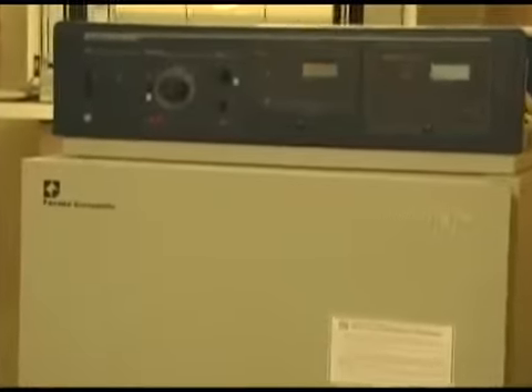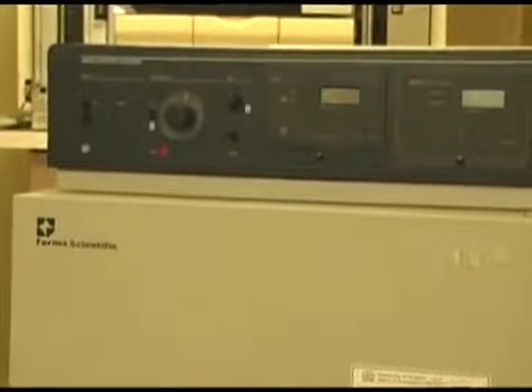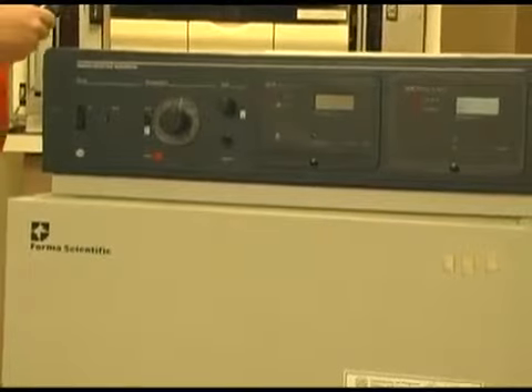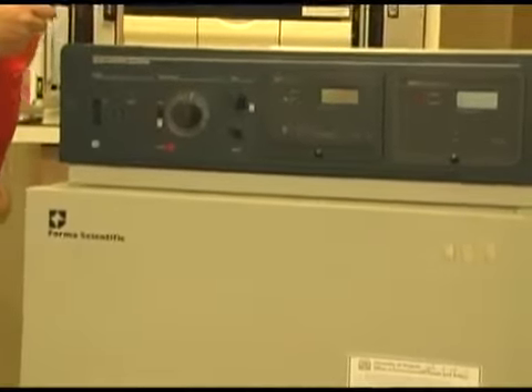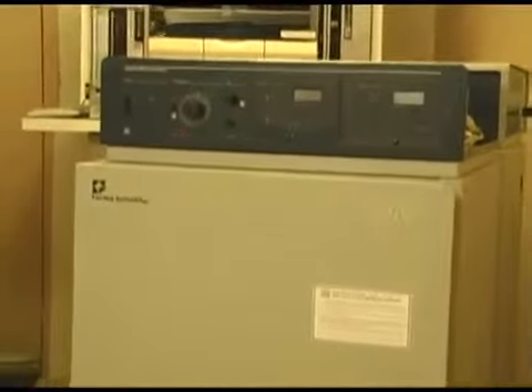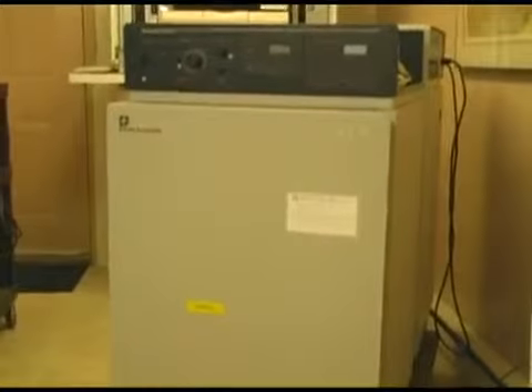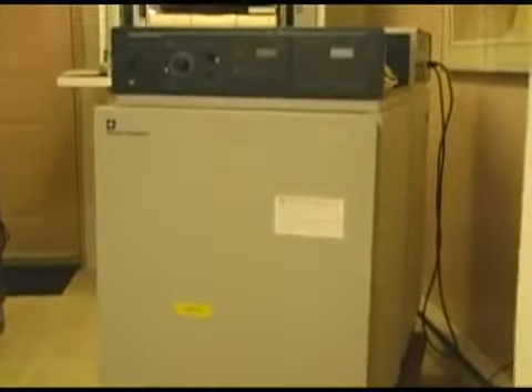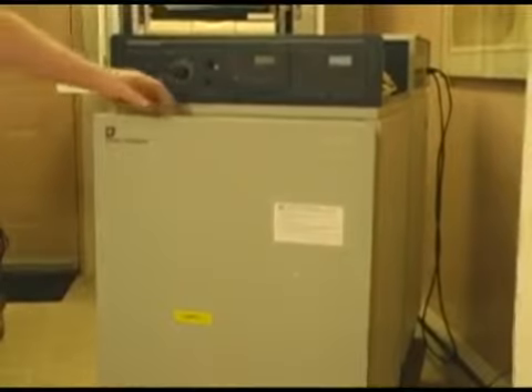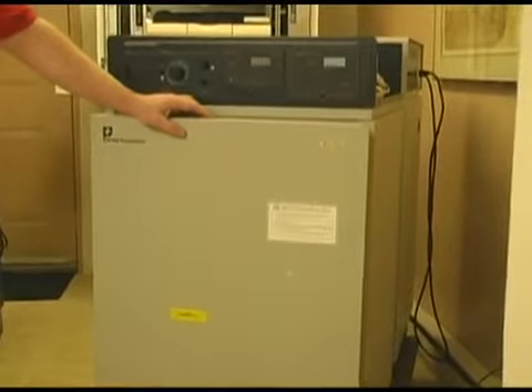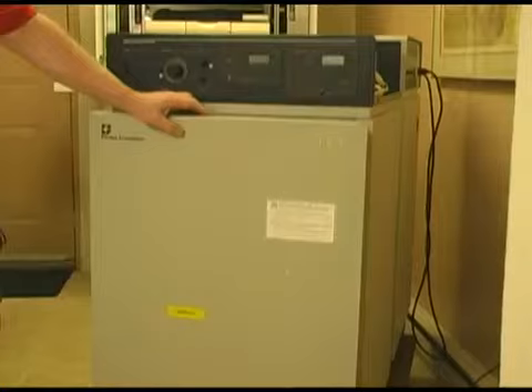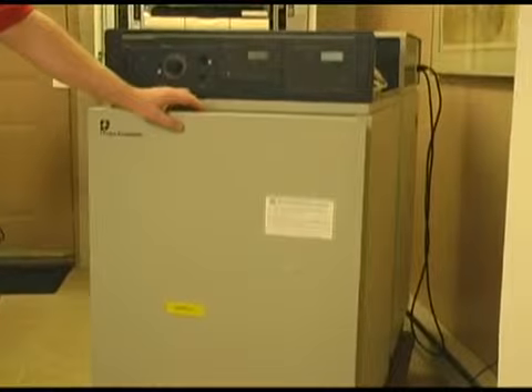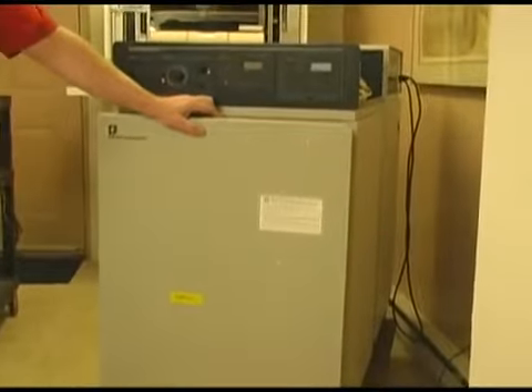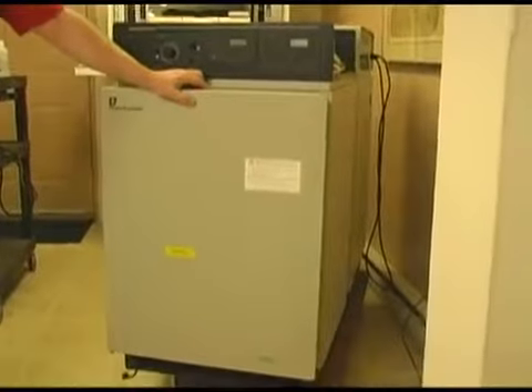We are going to be using the Forma Scientific incubator, model number 3158. It's a fairly old incubator, an extremely easy incubator to troubleshoot and repair. First things, all incubators have one thing in common: they all have chambers. Those chambers can be heated in two ways. They could be air or a water jacket.